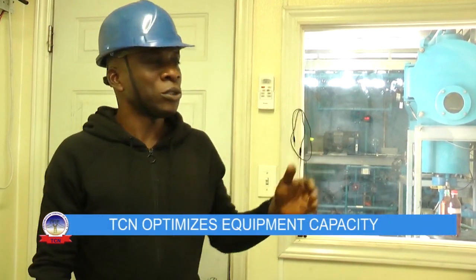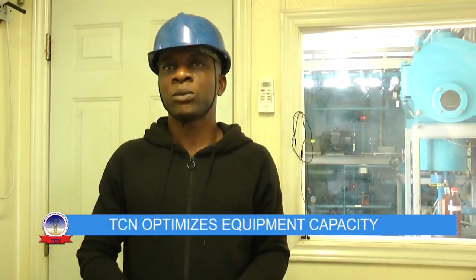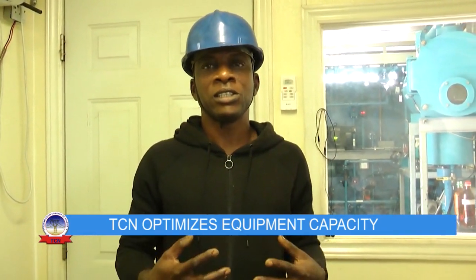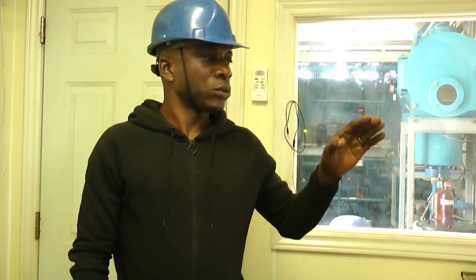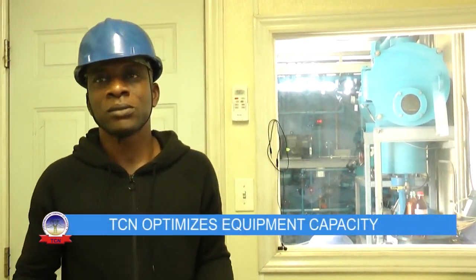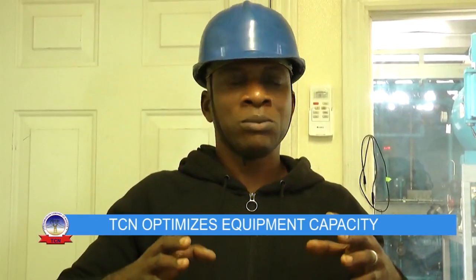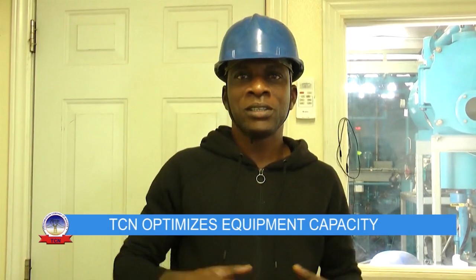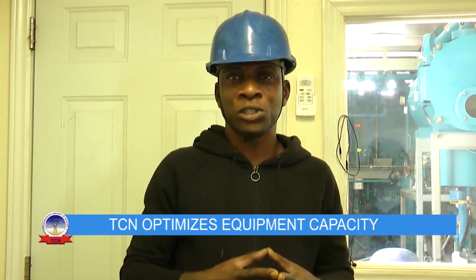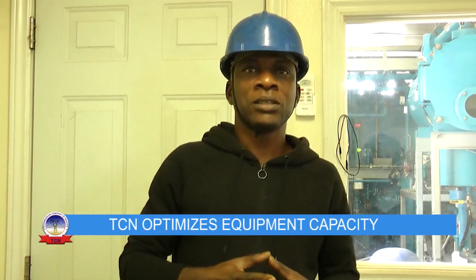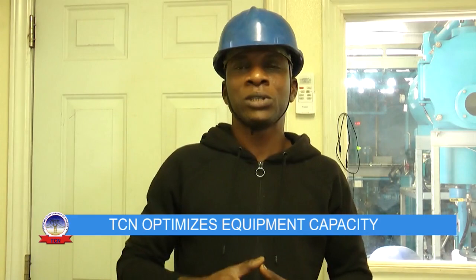The power circuit crew also spoke with the engineer operating the regeneration system machine known in the power industry as RSM. I'm here for regeneration, the regen of this transformer oil, to remove the sludge, the water content, the acid in the transformer, and to give the transformer the energy to perform more actively. What this machine does is remove the sludge, the acidic content, and the water present in the transformer, and give it the dielectric strength to increase it. For example, maybe it's 1 gig already, and if we increase it to 2 gig, 4 gig, or 5 gig, that's all.